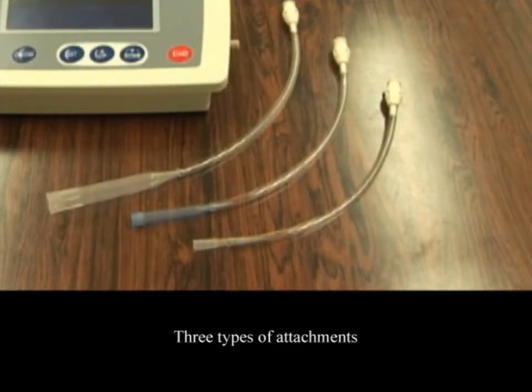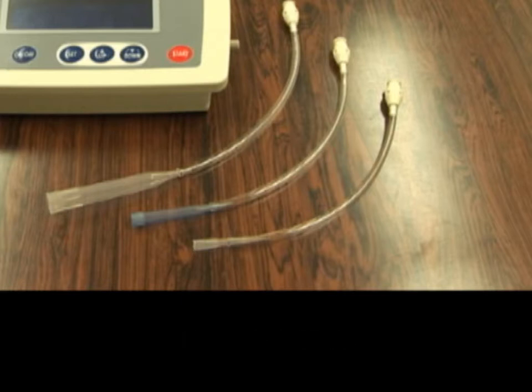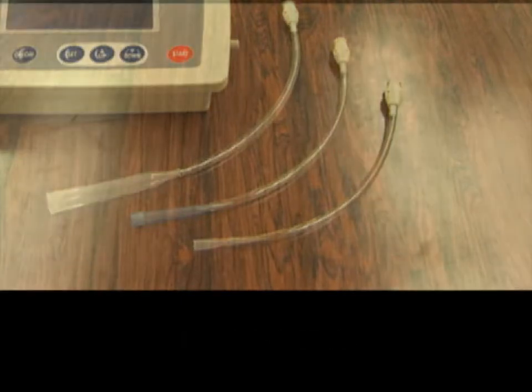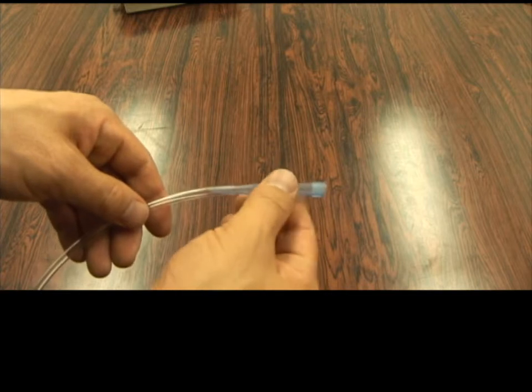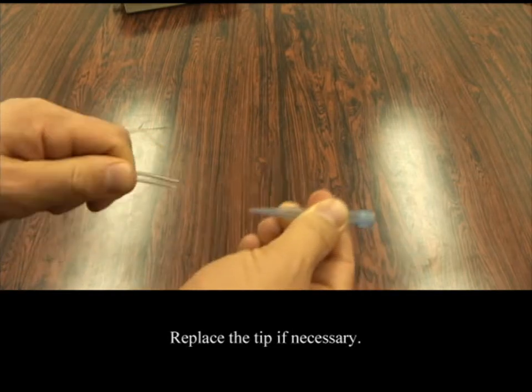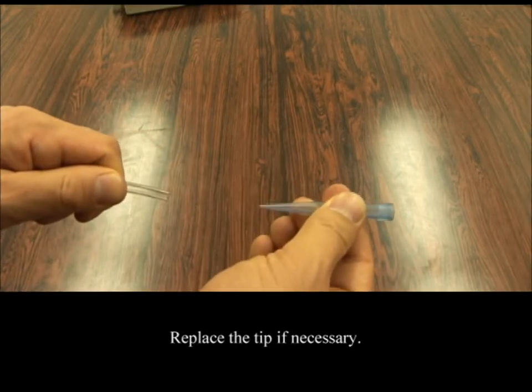The AD1690 includes three types of attachments to cover pipette capacities ranging from 2 microliters to 10,000 microliters. If your pipette does not match up with any of the attachments provided, replace the tip of the attachment with a tip that matches the pipette.